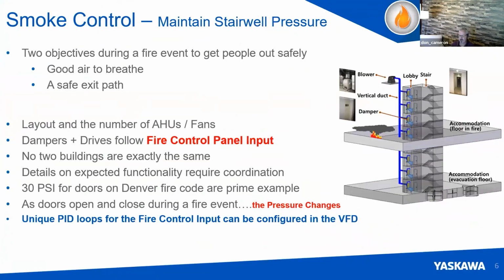So smoke control, as most folks know, if they've looked at this at all, smoke really causes more damage in the exit of occupants of the building than the fire itself. So maintaining the correct stairwell pressure is very, very critical to allowing occupants to leave and get good air to breathe and have a safe path to exit. You could probably spend an hour or 2 hours explaining the many different scenarios about air handler layout, how you set up these controls, but we don't have an hour and a half, right?